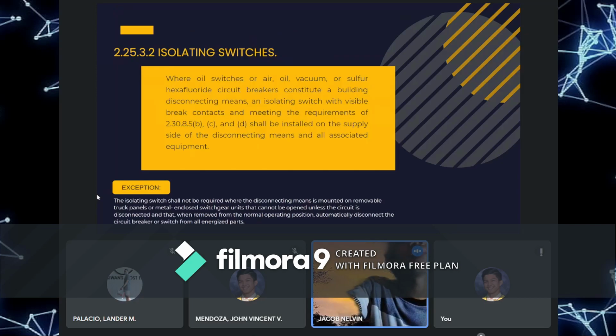Sa 2.25.3.2, which is the isolating switches. Sabi dito, where oil switches or air, oil, vacuum, or sulfur hexafluoride circuit breakers constitute a building disconnecting means, an isolating switch with visible break contacts and meeting the requirements of 2.30.8.5b, C, and D shall be installed on the supply side of the disconnecting means and all associated equipment. Dito sa 2.25.3.2 na isolating switches natin, may exception din.